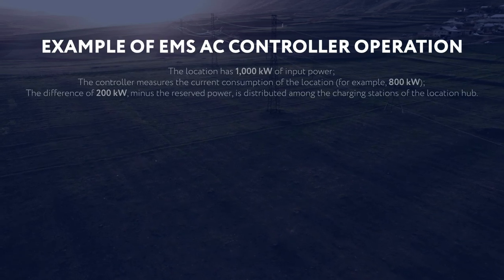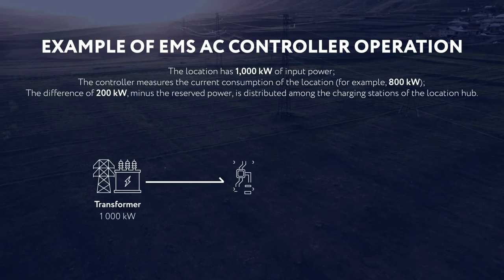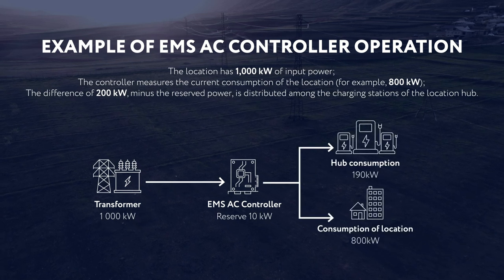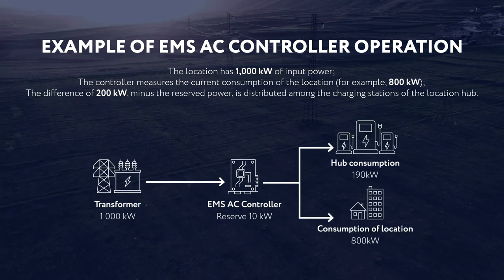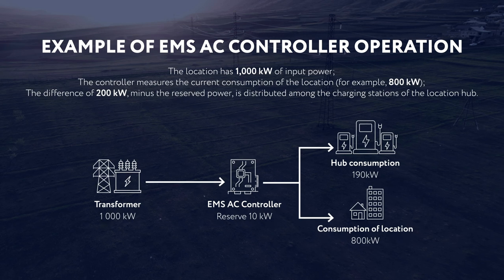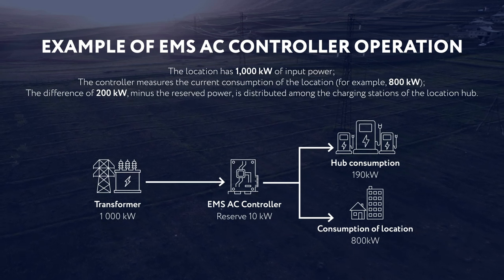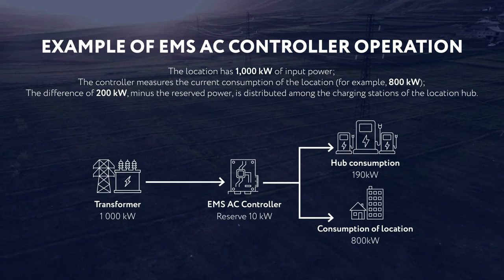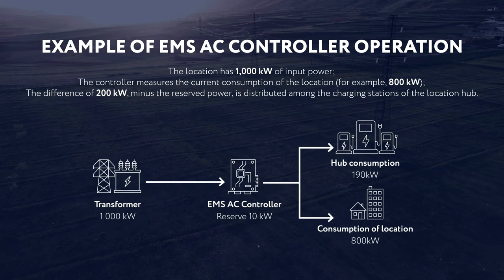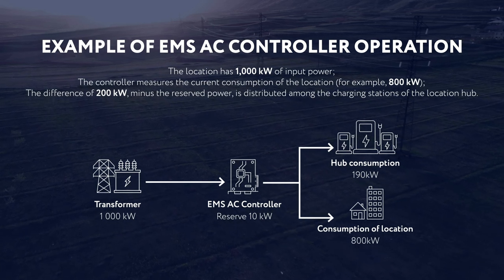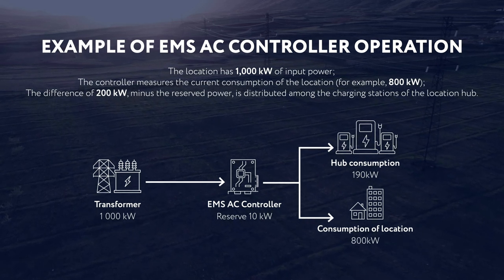Let's take a look at how the controller works with an example. The location has 1,000 kilowatts of input power, but is currently using only 800 kilowatts. The difference of 200 kilowatts, excluding the reserved power, is distributed among the charging stations at the location.